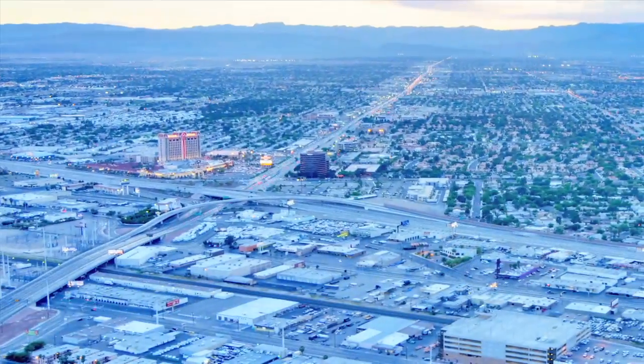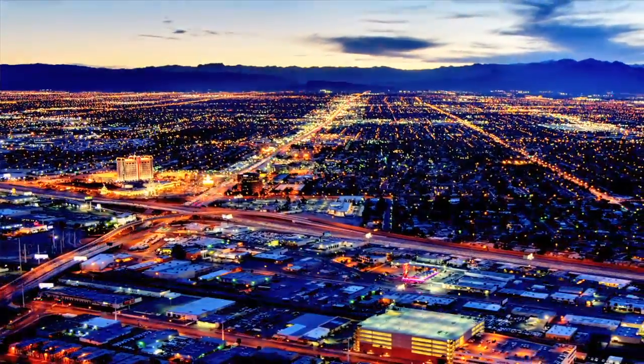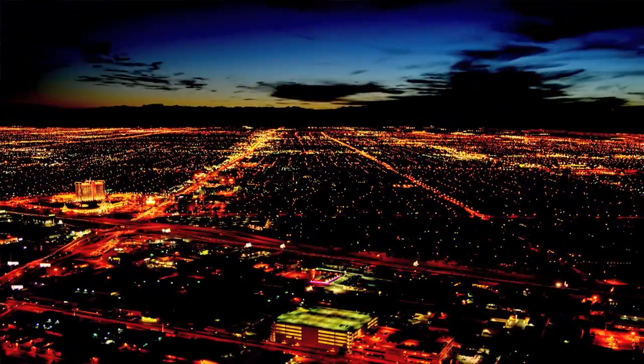David, from an energy-saving point of view, NECA contractors help their clients save energy. What type of energy savings does LED present to, say, a school or a city? You're not only saving on the lighting but also possibly on air conditioning cost. Any reduction in heat in a room saves you air conditioning cost. I would say LED can save you between 50 and 70 percent on the lighting electrical portion of your bill. Some cities we've talked to are running a couple million dollars in lighting bills — that saves them a million dollars a year at 50 percent. I would conservatively say 50 to 60 percent savings on your electrical cost on lighting.